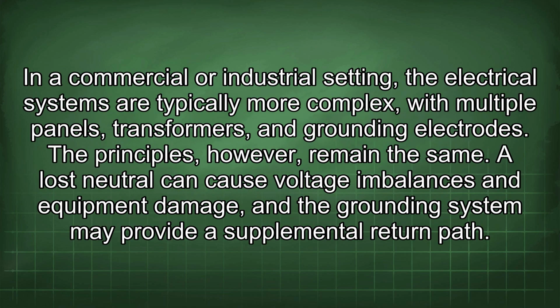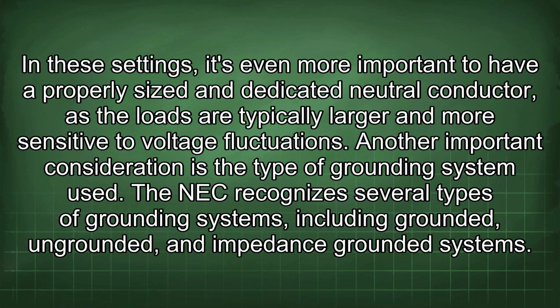In a commercial or industrial setting, the electrical systems are typically more complex, with multiple panels, transformers, and grounding electrodes. The principles, however, remain the same. A lost neutral can cause voltage imbalances and equipment damage, and the grounding system may provide a supplemental return path. In these settings, it's even more important to have a properly sized and dedicated neutral conductor, as the loads are typically larger and more sensitive to voltage fluctuations.